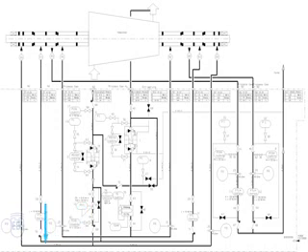When a labyrinth seal is selected, a buffer gas flow rate across the labyrinth of at least 10 meters per second is obligate. To use an orifice is the easiest way to achieve this.